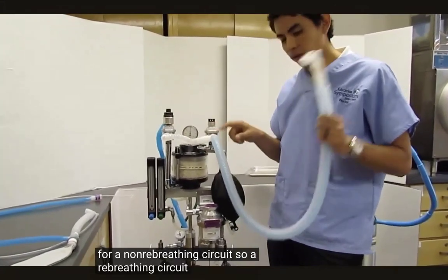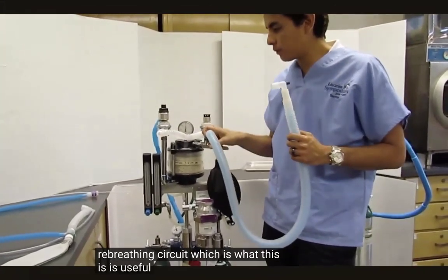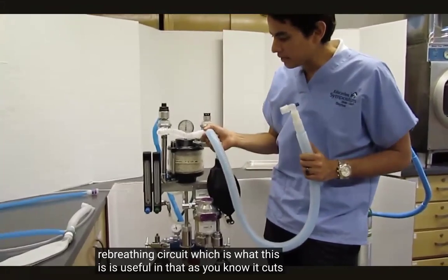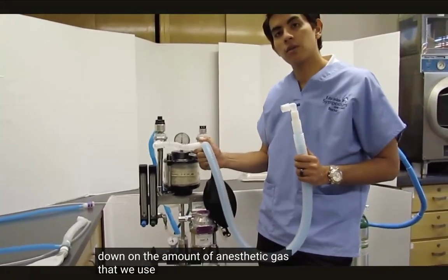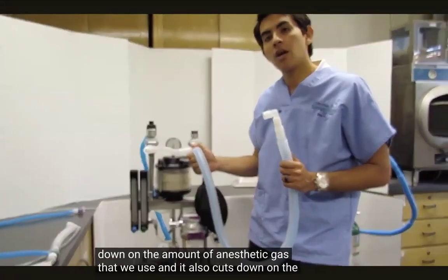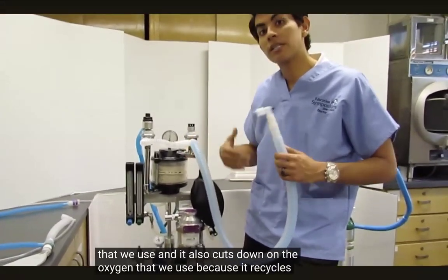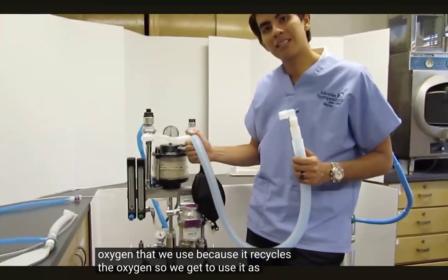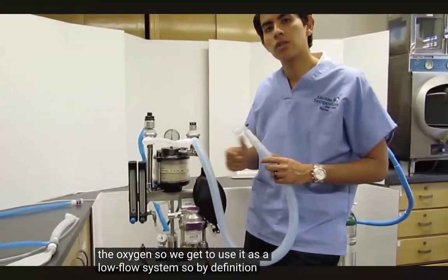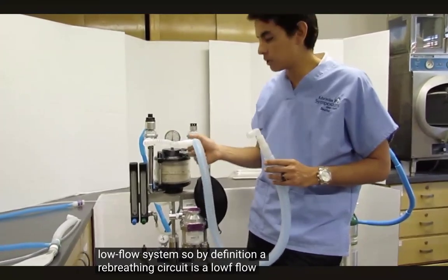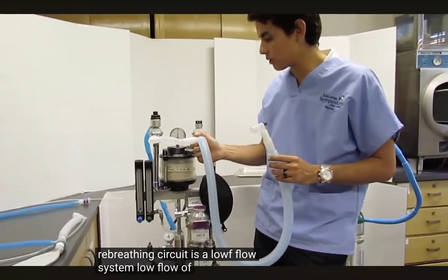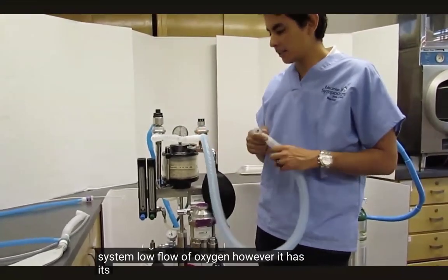So a rebreathing circuit, which is what this is, is useful in that, as you know, it cuts down on the amount of anesthetic gas that we use, and it also cuts down on the oxygen that we use because it recycles the oxygen. So we get to use it as a low flow system. By definition, a rebreathing circuit is a low flow system, low flow of oxygen. However, it has its disadvantages.